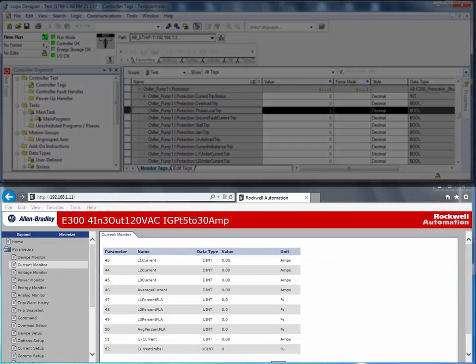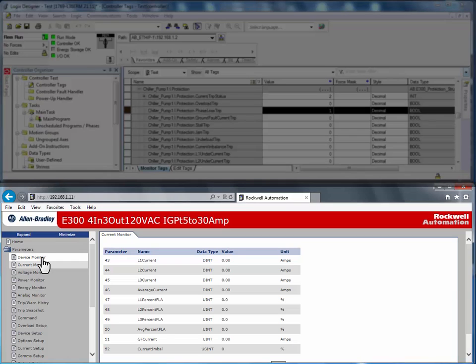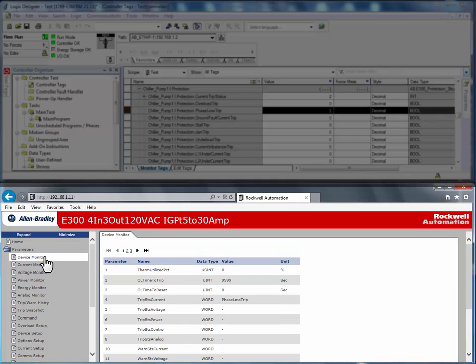This information can also be found on the web server. By monitoring the device status, we can see that the E300 had a phase loss trip.